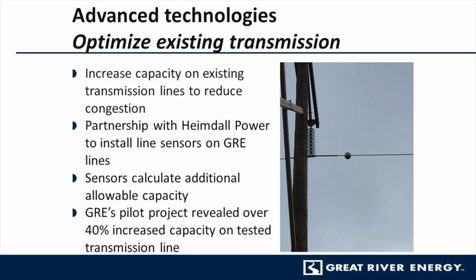Most utilities like Great River Energy operate transmission lines using static ratings. We identify really conservative limits for our lines, because we want to make sure the line can safely carry power without overheating. We use those static ratings in planning and in operations, and they're conservative - all utilities have done that forever.